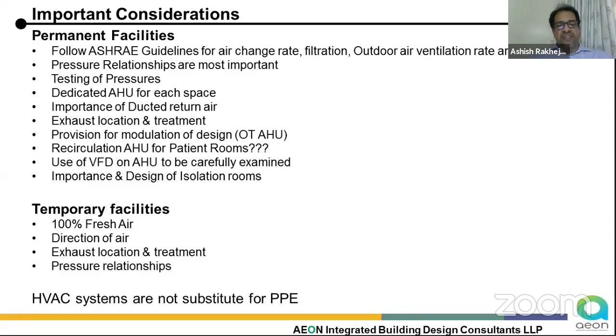Finally, to end it, for temporary facilities which are required, which are the need of the day, one of the good solutions is to move towards higher fresh air rates. If we are not able to put better filters into them, of course, we can upgrade the filters easily to MERV 13, MERV 14 without any challenge. There are good electrostatic precipitators and all which are available, which do not create any additional resistance to the airflow. Just by removing the existing filters, you can easily retrofit within a few days' time. You can increase the fresh air quantity, make the airflow directional, make sure the exhausts are being correctly put, the negative spaces are being created as per the guidelines which are available, and we are able to maintain the pressure relationships.